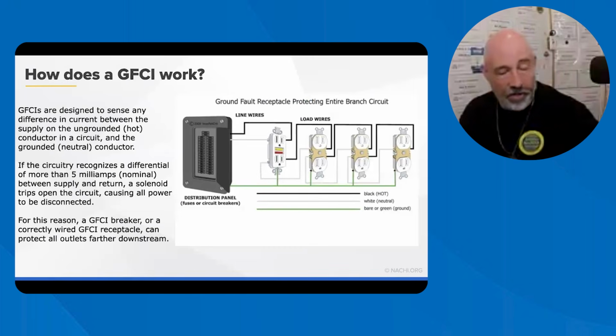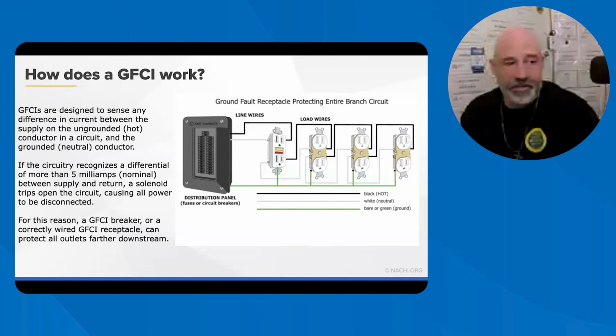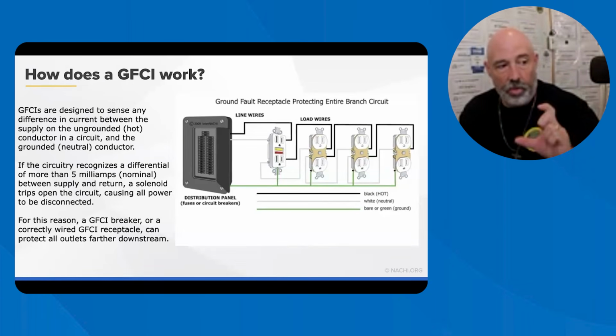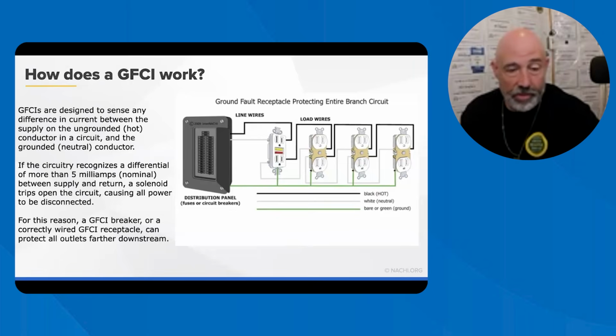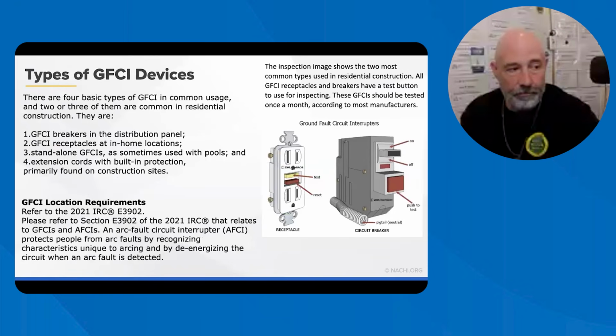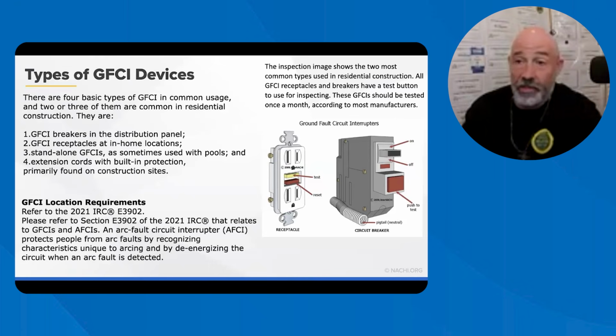So you can always daisy chain them down. Remember, we talked about the line in, and then you have your load wires, and those push out past wherever that GFCI is. So that's kind of how they work. That's why the ones in the panel are a lot easier to install. Types of GFCIs, here are the two that are most common, the ones that are in the panel itself and ones that are push button. And we've seen probably both of them if you've been inspecting for more than 5 days.